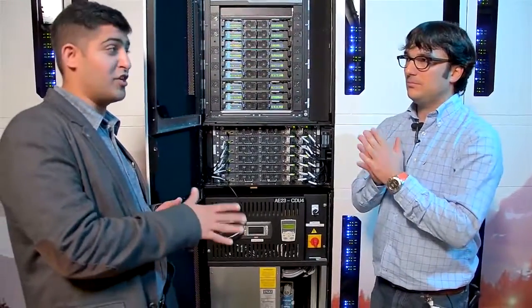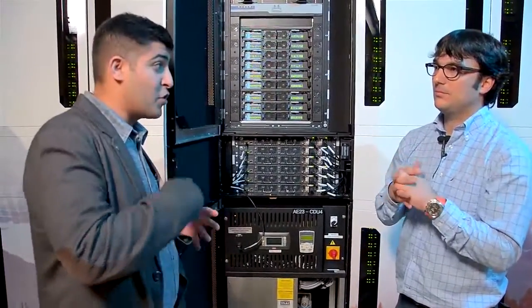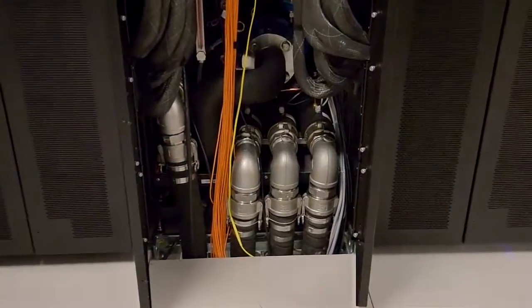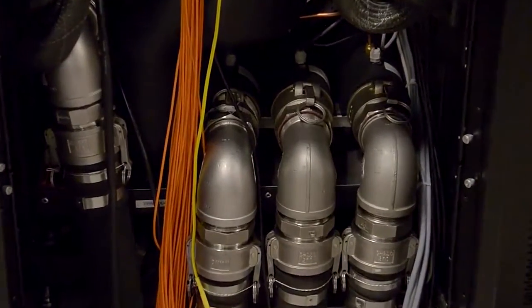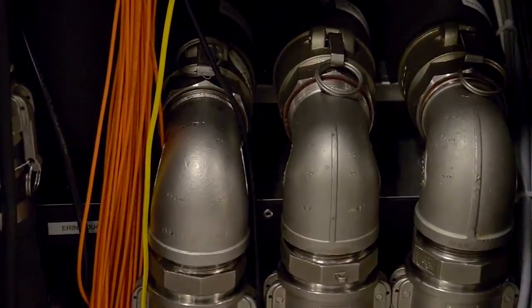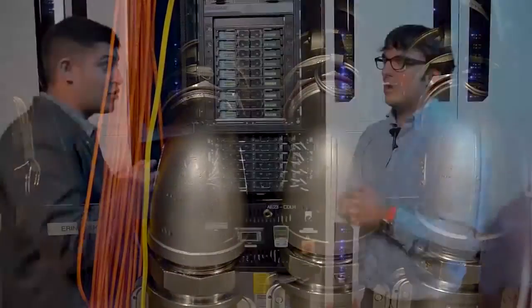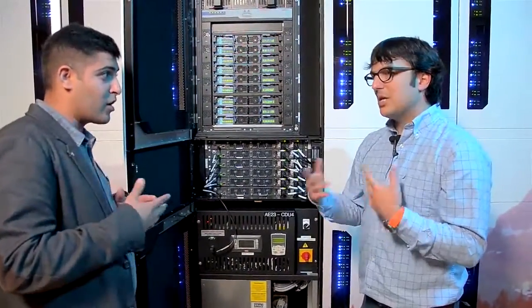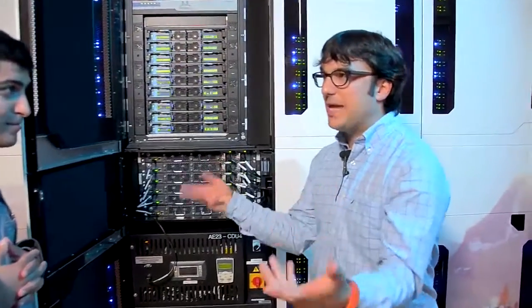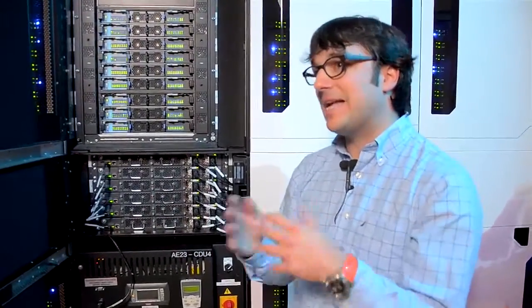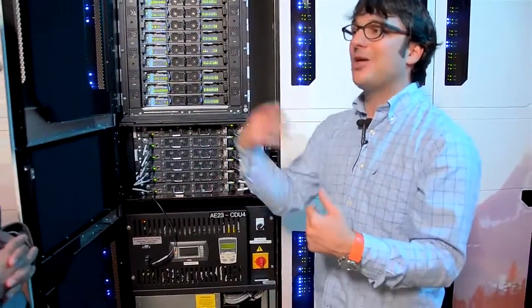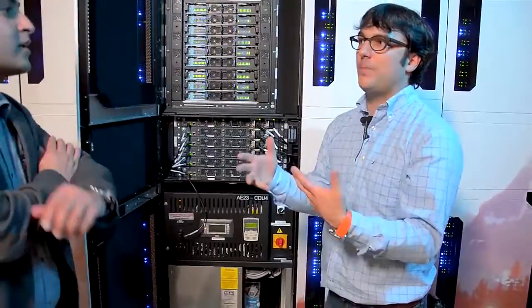This is a key piece of our technology—we're making sure we address the nervousness customers have around liquid-cooled technologies in the data center, specifically water leakages. So HP has a way to mitigate that risk and ensure there's no leakage? That's the secret sauce. Not only do we have the dry disconnect, which we believe is actually much safer from a water leak perspective than anything else out there, but on top of that, we run the secondary loop out of a vacuum.